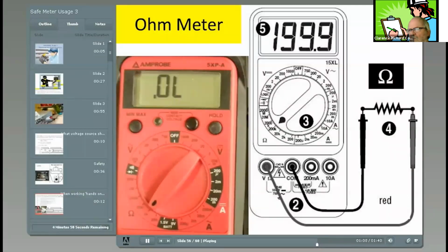If the ohm meter is connected to a circuit where power is on, the meter can be damaged, besides giving the wrong reading. An ohm meter has its own internal battery, and the power must be off in the circuit being tested. The ohm meter is helpful in checking the continuity of any wire conductor. Also, any coil for a transformer, solenoid, or motor will have infinite resistance if the winding is open. In this particular case, the range is set too low, indicating the operator must move it up until he gets a reading.